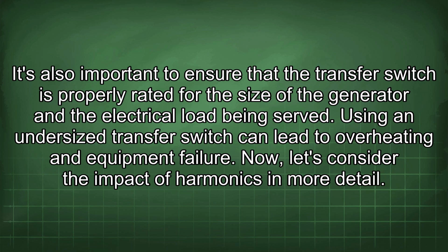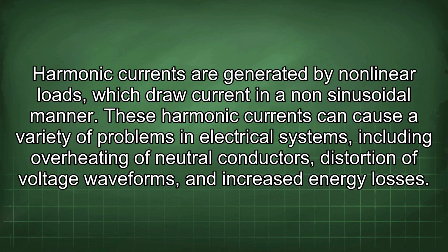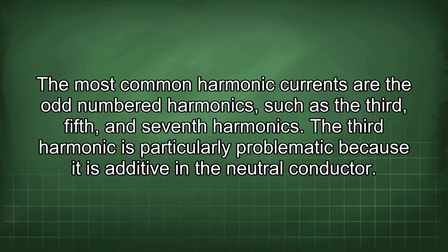Now let's consider the impact of harmonics in more detail. Harmonic currents are generated by nonlinear loads, which draw current in a non-sinusoidal manner. These harmonic currents can cause a variety of problems in electrical systems, including overheating of neutral conductors, distortion of voltage waveforms, and increased energy losses. The most common harmonic currents are the odd-numbered harmonics, such as the third, fifth, and seventh harmonics.